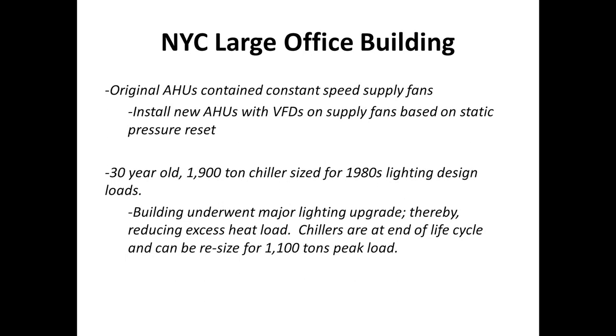Along with these new air handling units, they also installed VFDs and put in static pressure reset. So as the VAV boxes closed, the static pressure built up in the supply ductwork. The VFD on the supply fan was allowed to ramp down, saving on fan energy usage.